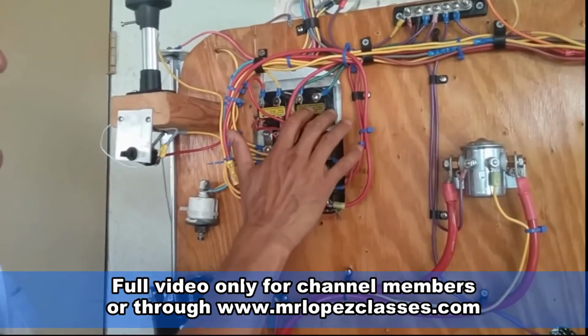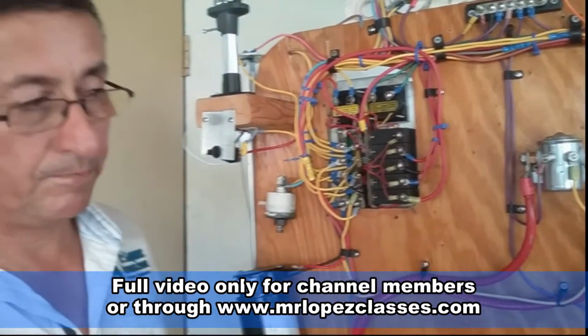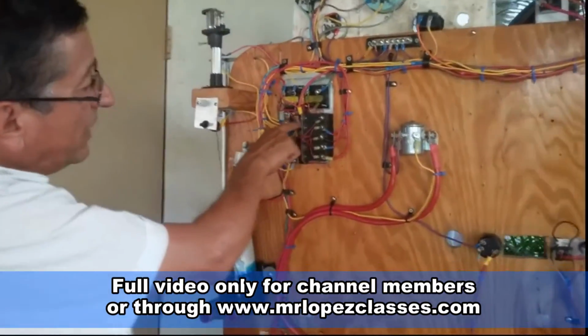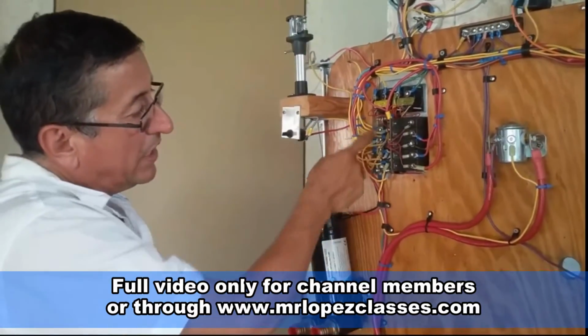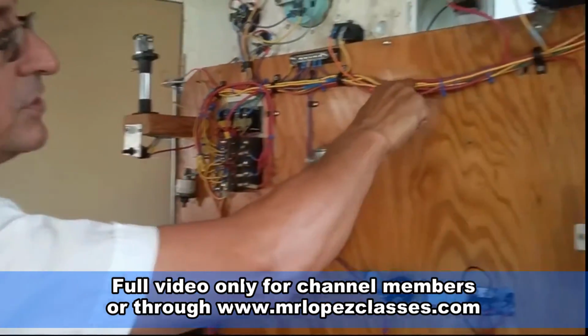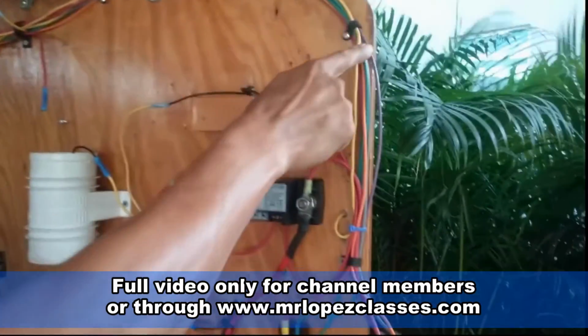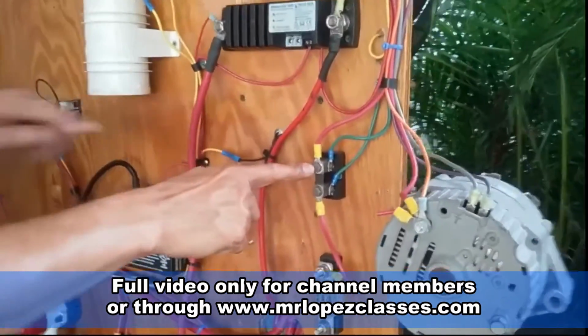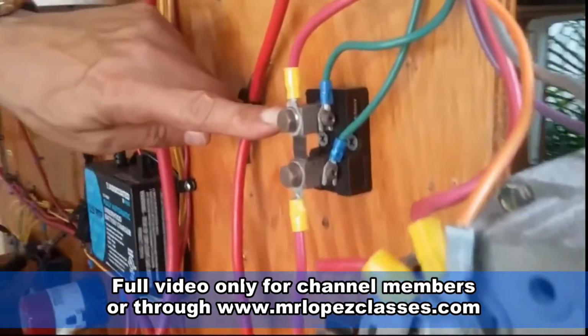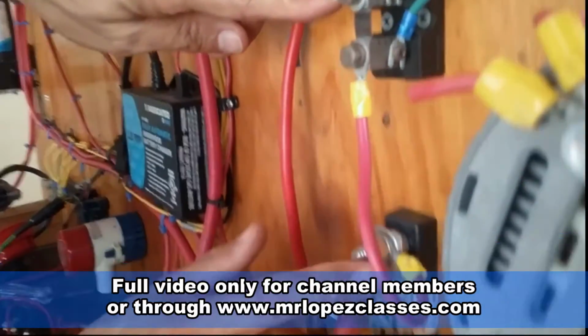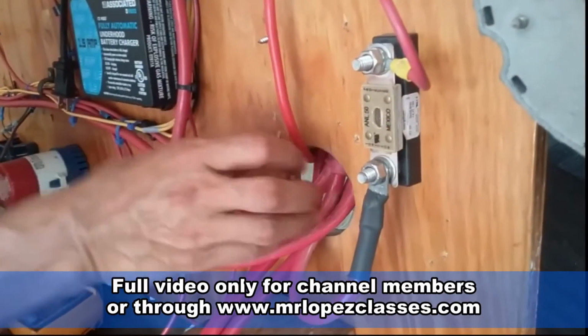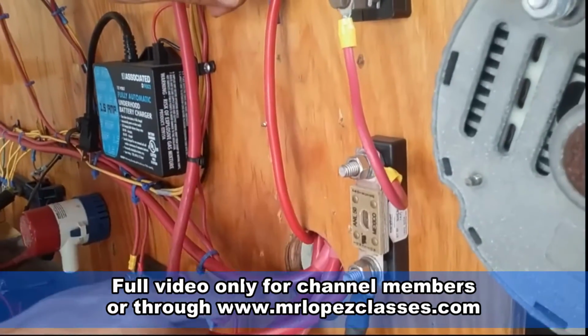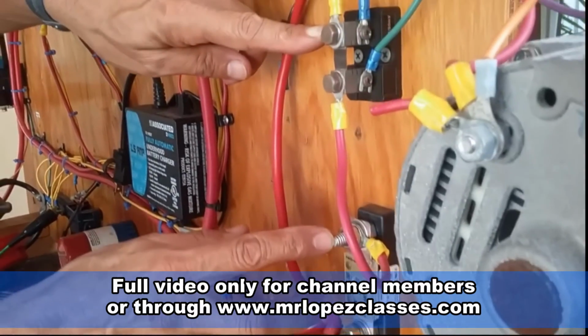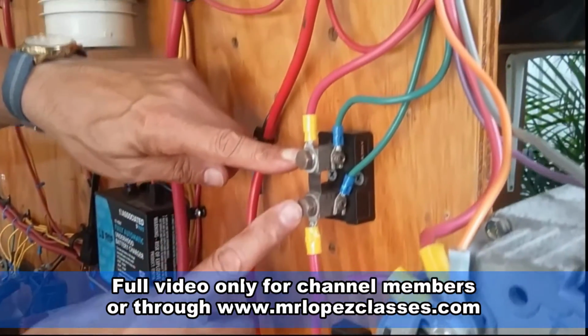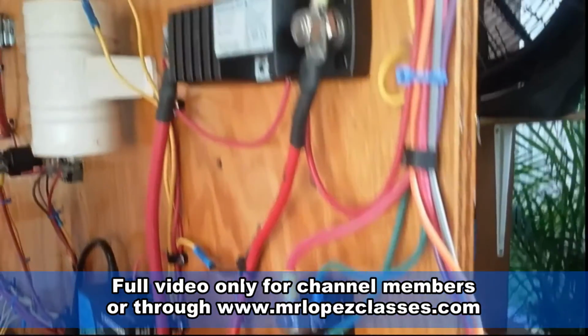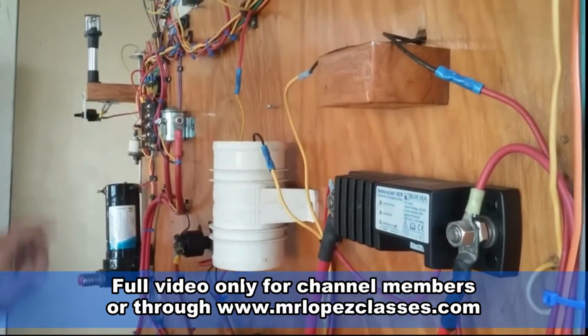Once again, let me explain how this ammeter is connected. You remember the positive cable to enter the positive bus bar? That's the positive cable, here. This is the shunt, and this is the other end. It enters into the fuse and goes into the switch selector. Okay, this is the power coming from the battery, passing through the fuse, and after the fuse, entering the shunt and continuing into the positive bus bar of the panel.